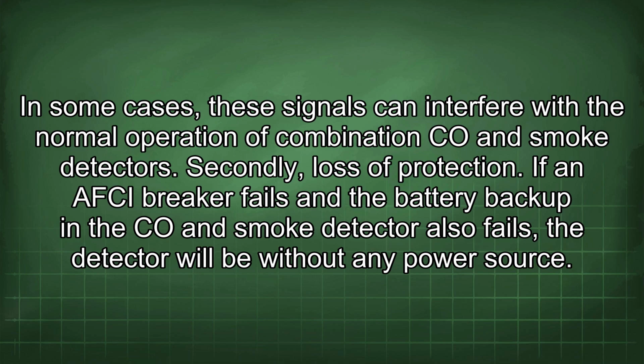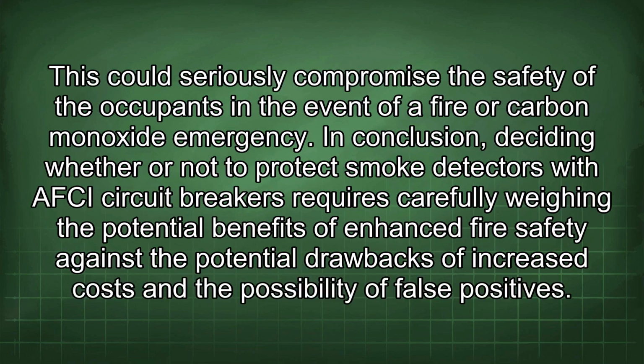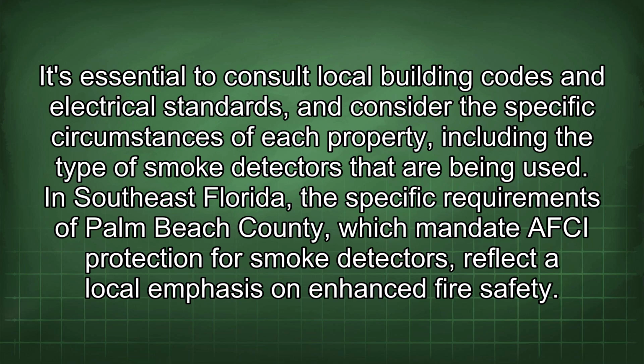Secondly, loss of protection. If an AFCI breaker fails and the battery backup in the CO and smoke detector also fails, the detector will be without any power source. This could seriously compromise the safety of the occupants in the event of a fire or carbon monoxide emergency. In conclusion, deciding whether or not to protect smoke detectors with AFCI circuit breakers requires carefully weighing the potential benefits of enhanced fire safety against the potential drawbacks of increased cost and the possibility of false positives. It's essential to consult local building codes and electrical standards and consider the specific circumstances of each property, including the type of smoke detectors that are being used.